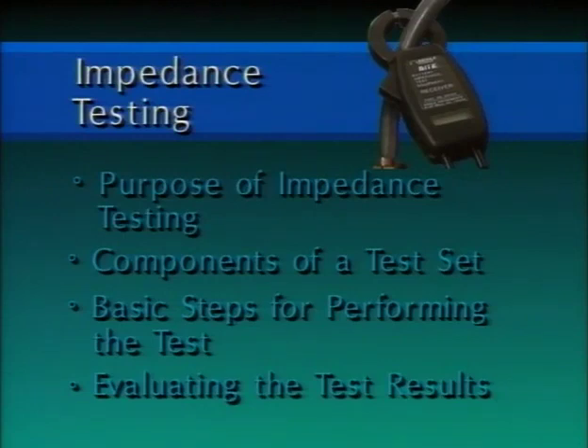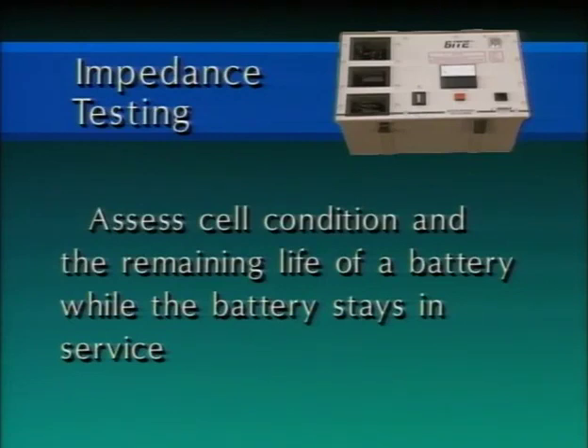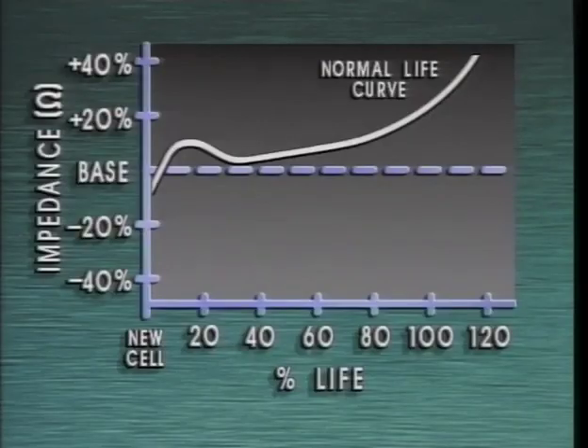The key points that will be covered include the purpose of battery impedance testing, the components of an impedance test set, the basic steps for performing the test, and evaluating the test results. The purpose of battery impedance testing is to assess cell condition and the remaining life of a battery while the battery stays in service. The value of measuring cell impedances is based on the principle that cell impedances increase as the battery's capacity decreases. This chart shows a typical curve of cell impedance over the life of the cell.